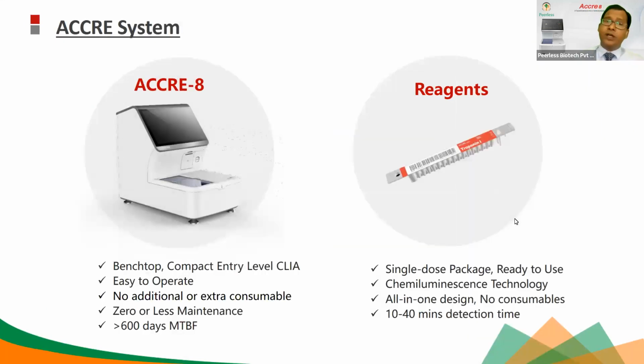Going into a little more detail. This is a benchtop and compact entry-level chemiluminescence immunoanalyzer, as we said. Apart from that, it is quite easy to operate. The operation is very easy, as I said. No additional cost or extra consumables. That is the most key factor while we promote this instrument. So I repeat, there is no additional cost or extra consumable within the machine. In CLIA, many companies quote cost per test, but there are hidden costs like buffer, diluent, sample pre-diluent, quality control, calibrator. There are multiple things which customers have to purchase separately, which no one mentions while selling. But here, what we are providing is everything along with it. I'll show you in the reagent segment once I show you the real photographs.